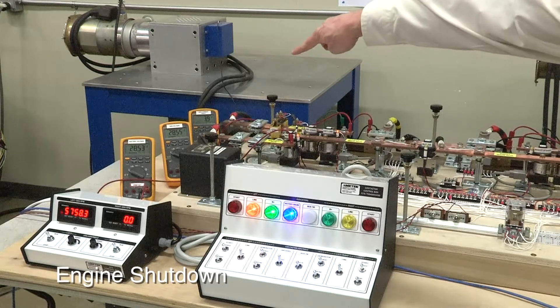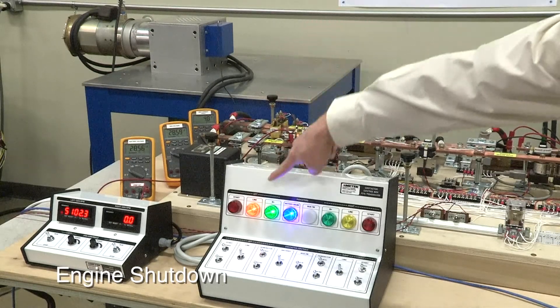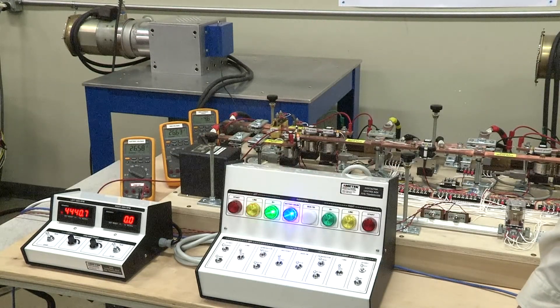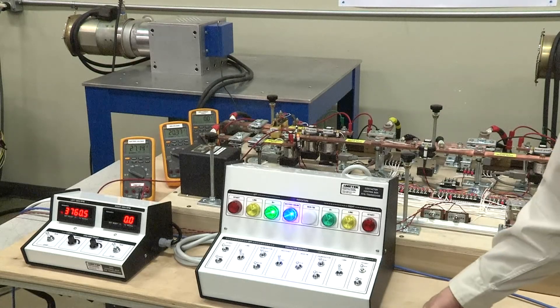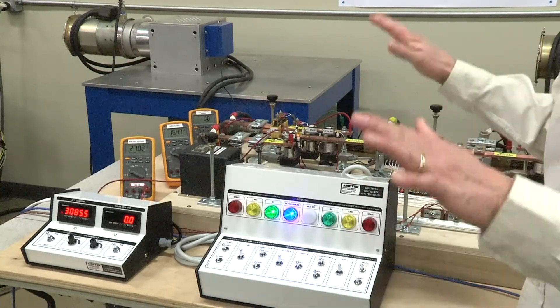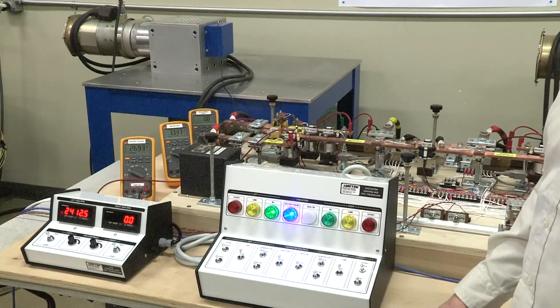All right, you can watch the voltage here. You're going to see the voltage drop off and the line contactor trip open. So we've lost voltage regulation and the engines are spooling down to zero again.